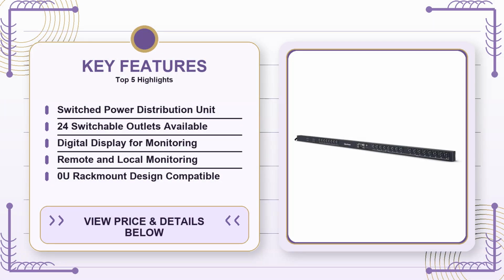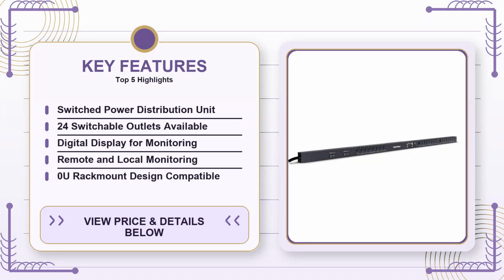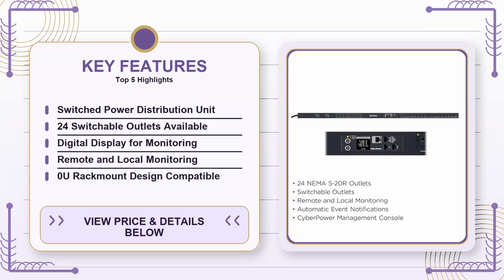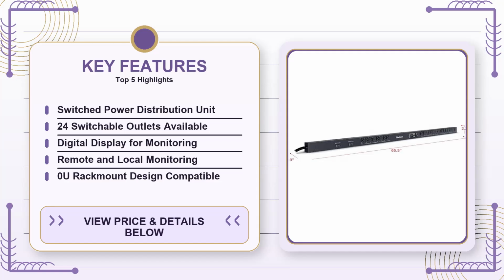However, there are a few practical weaknesses you should be aware of before you click Add to Cart. The first is the lack of surge protection. The PDU is essentially a switched strip. It doesn't provide any line-level filtering or surge suppression. If your facility experiences power spikes or you're in a region with unreliable mains quality, you'll need to place a separate surge protector upstream, which adds another component and potentially another point of failure.